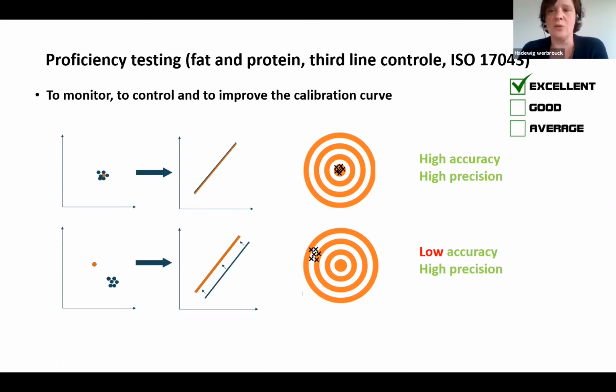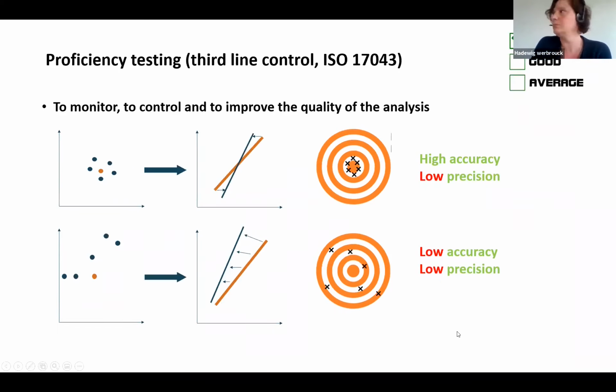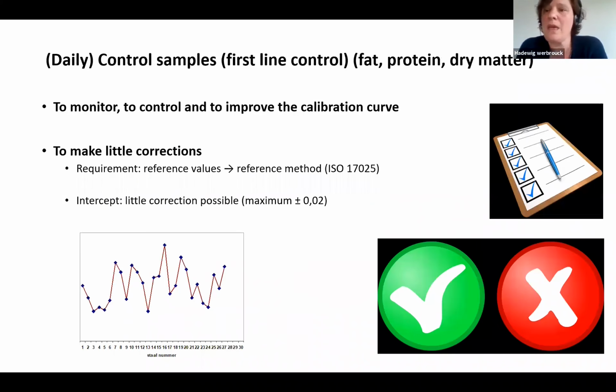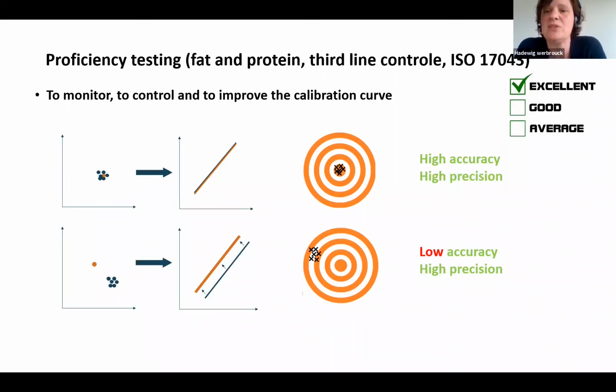The first one is a high accuracy and a high precision. This means that the results of the repetitions are close to each other and that all these values, the blue dots, are also close to the reference value, the orange dot. When this is also the case for other concentrations, the slope and the intercept of the calibration are fine. The second possibility is a low accuracy and a high precision. In this situation, the repetitions are close to each other, but the results are far from the reference values. If this is also the case for other concentrations, a shift of the calibration line is observed.